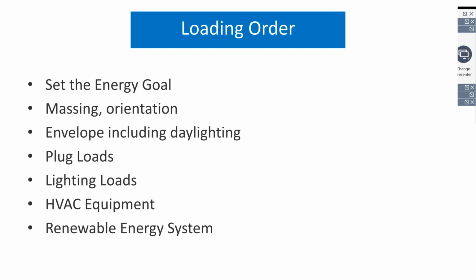The lighting loads - getting those down - LED technologies have really helped with getting lighting power densities well under 0.5 watts a square foot. And again, getting those lights off when there's adequate daylighting in spaces, or dimmed when there's good daylighting, and especially getting it off when the building is not occupied. Once you have all those pieces down, I'd almost like to draw a line there.